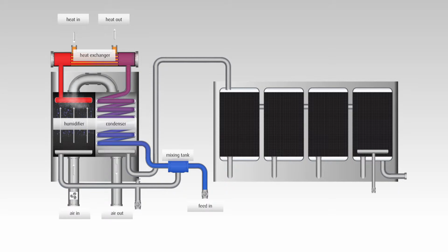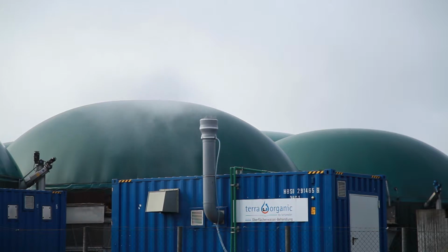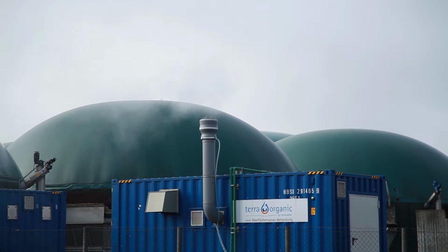During the process, the air is heated and wetted. The extremely humid air flows into the condenser, where it cools down at the tubes with the cooler feed water, and water is separated from the air by way of condensation. At the same time, the condensation heat is used for preheating the feed water in the tubes, which adds up to the system efficiency. The condensate is collected in a tank and is then ready for further use. The cooler air is released into the environment.